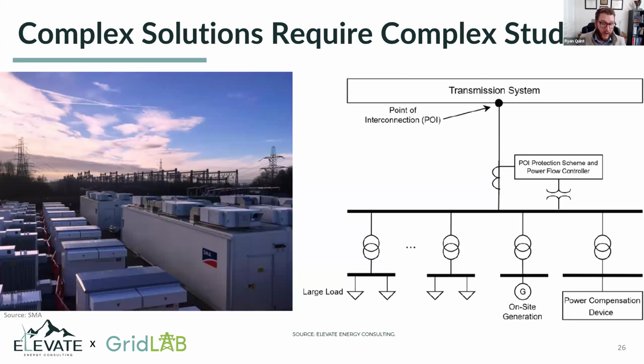On the next slide, there are other more complex reliability studies to consider, where you've got entire energy parks, including generation and large load customers, with multiple connections to the grid across the park, making sure those align with the transmission capacity being used. So if I'm building, say, an 800 megawatt data center but only have 100 megawatts of transmission capacity, and I lose my generator or portions of my data center, I've got to make sure I'm not causing issues on the transmission system.